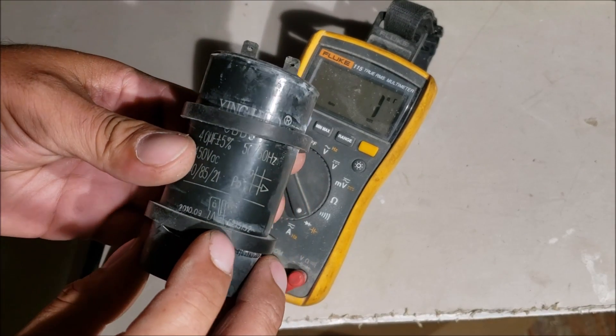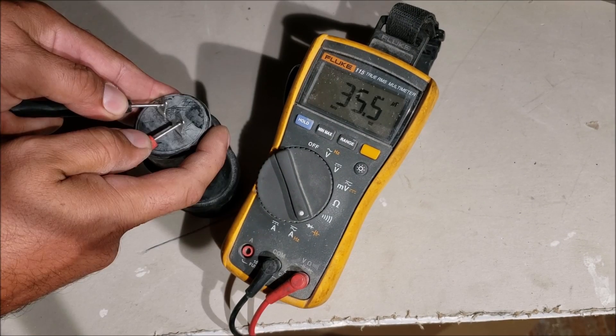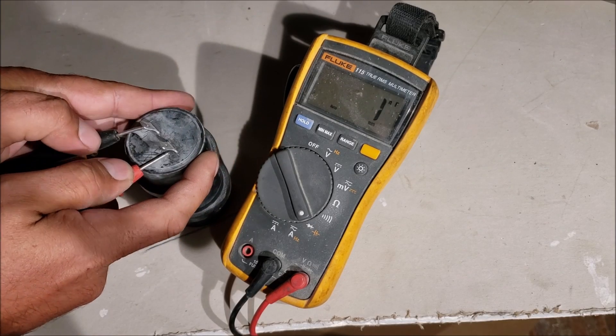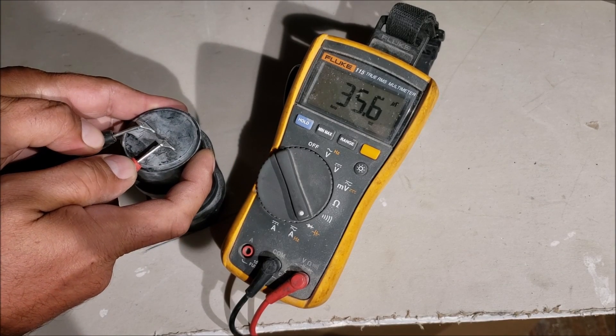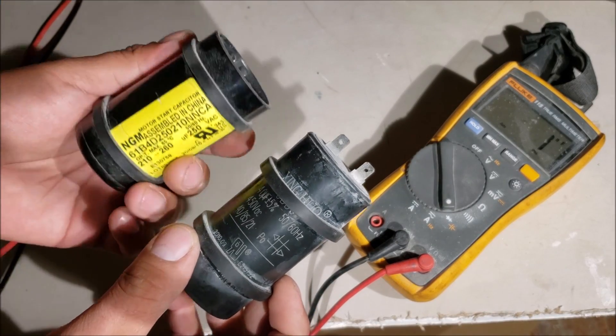Let's test it: 35.5. Flip it, play around with it, do it a few times. This is very interesting because this is an air compressor that I got from work that is bad. It starts up and trips the breaker, and guess what we just found?